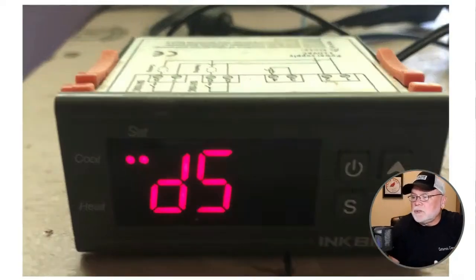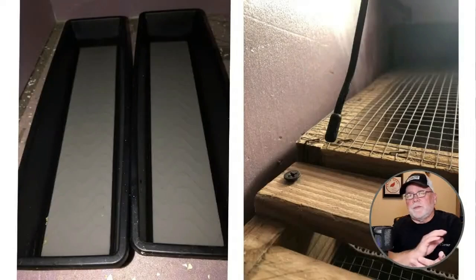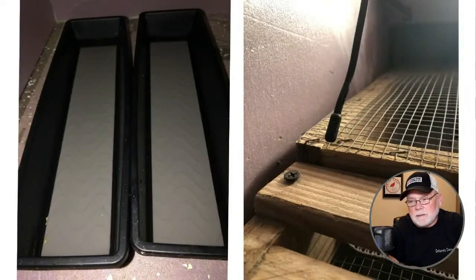Okay, next setting is DS, which stands for differential set. And that is the amount of degrees that you want it to drop. You've got to set it at 99, and you want to set this differential set to 1. That means it will drop 1 degree before turning the light back on. So this value, I think by default, to be honest with you, I'm not sure what the default setting is, but that needs to be set at 1. That covers those settings inside the Inkbird. And the settings are really simple, guys. Once you get in there, there's, like I said, only 3. You've got your temperature, you've got your compressor delay, which needs to be at 0, and your differential set, which needs to be at 1. Those 3 settings, your Inkbird's set up and ready to go.